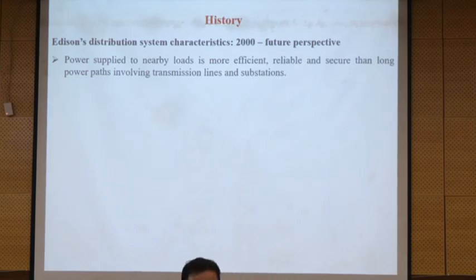Do you like the Edison model or not? The Edison model is close to the load center. It means consumption is close to generation, and you don't have any transmission and distribution line. So it means your system has fewer losses and is more secure, because when you don't have this type of transmission or distribution line, the event will not impact it. It is also more reliable, more efficient, more secure, more resilient - more anything you want to say.